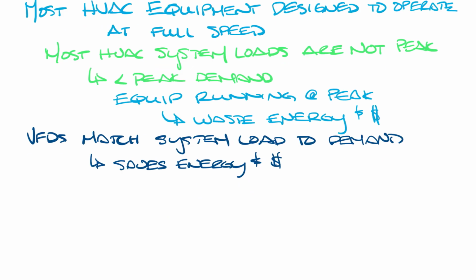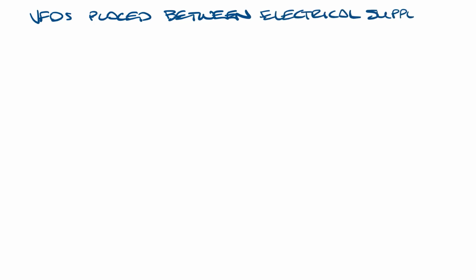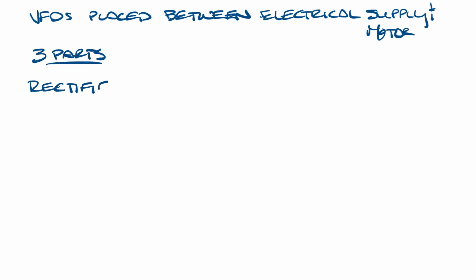So let's make some room and look at how they work. VFDs sit between the electrical supply and the motor. Power from the electrical supply goes into a drive, and then the drive regulates the power that is fed to the motor. There are basically three components in the VFD we need to talk about. First of all, inside the drive, the input power is run through a rectifier. That converts the incoming AC power to DC power.